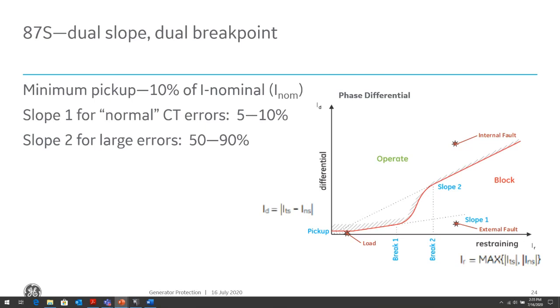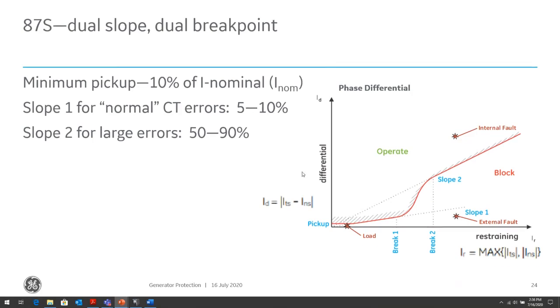So our slope can be set lower between our differential and our restraint. Now, when we're talking about maybe internal faults or close-in external faults where the CTs are subjected to high fault currents, it's more susceptible to having large differential ratio errors because one CT might saturate and the other CT has not saturated. On the relay, we'll see that as a fault current. What we do is we raise the slope setting for those scenarios so that we need a higher level of differential, so we can deal with a certain level of CT saturation and still reliably detect internal faults and restrain from tripping for external faults.